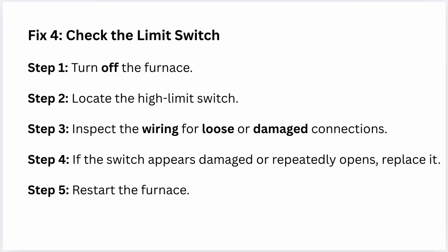Fourth one is check the limit switch. Turn off the furnace, then locate the high limit switch. Inspect the wiring for loose or damaged connection. Then if the switch appears damaged or repeatedly open, replace it, then restart the furnace.